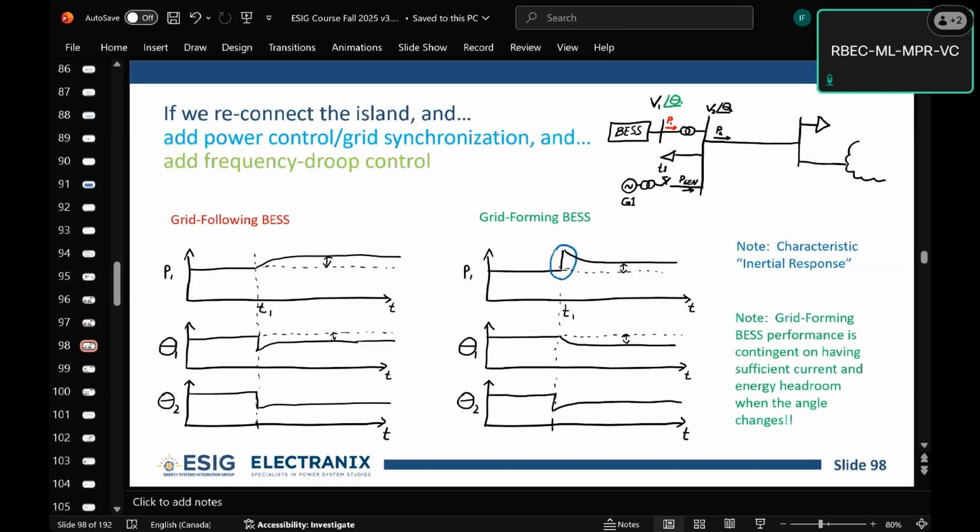That short period, that inertial response, or automatic physical response, is what gives us our small signal stability. It's basically resisting changes in the system and not allowing the controls to move quickly. So that's what gives it that very, very stable behavior in weak systems.